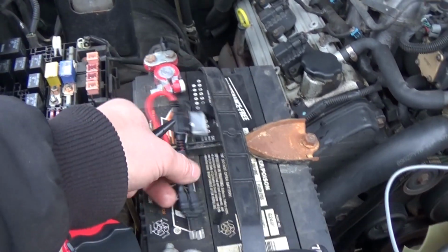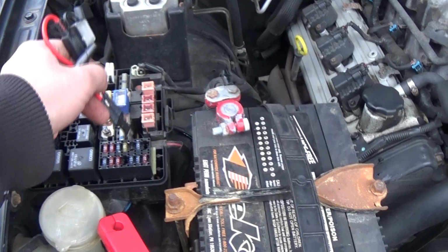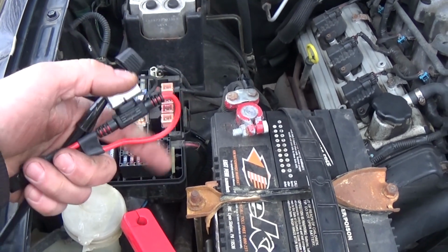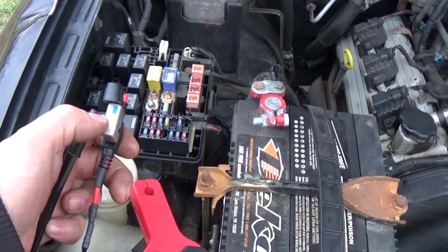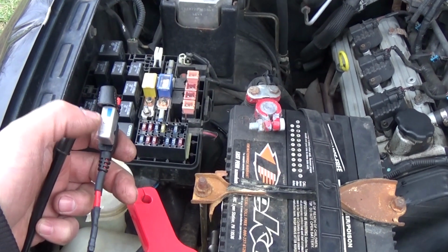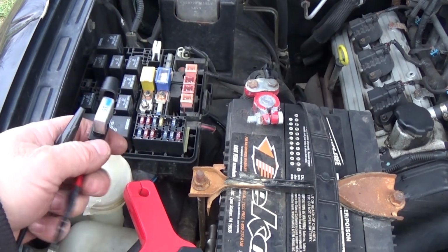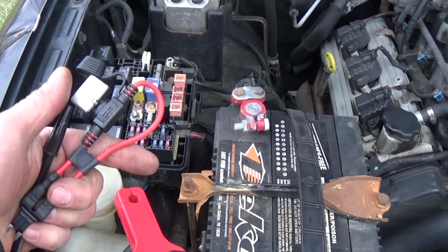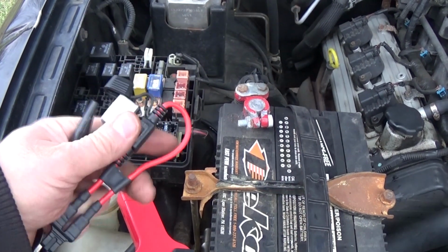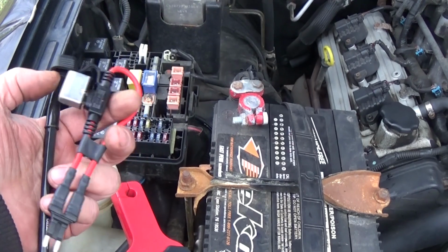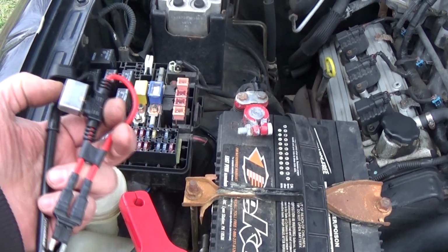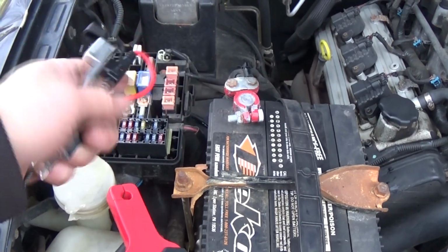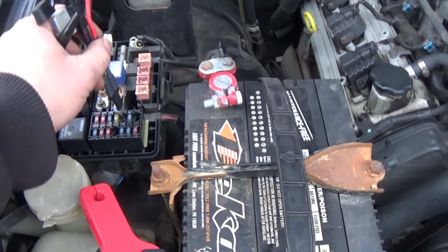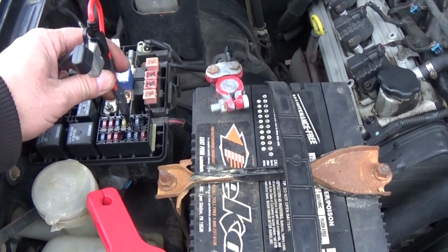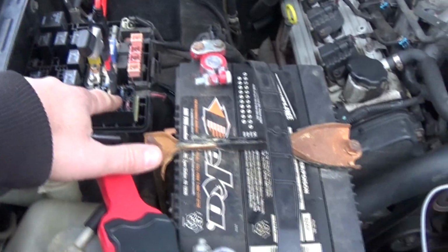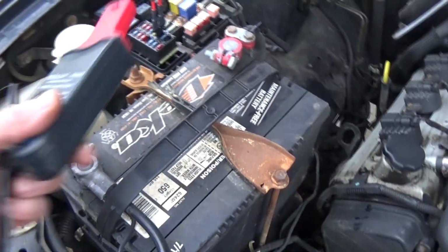So I have a fuse jumper here and a circuit breaker, this is a 15 amp. Even though it's a 20 amp circuit, it's okay—of course you want to use 20 or less. You can buy this for $1 or $2, it's a really nice device so you don't keep blowing your fuses instead of having a simple circuit breaker. I'm going to install that into this circuit, then get my amp clamp.